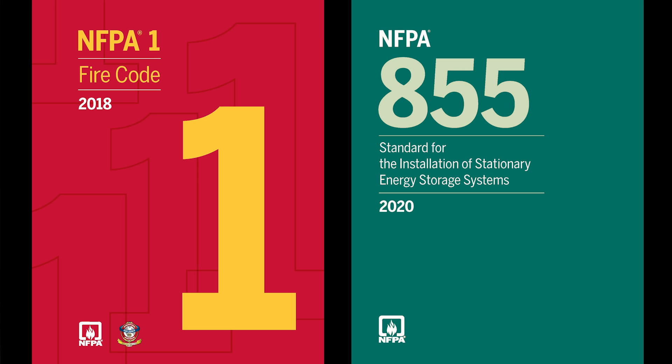The purpose of the UL 9540A test method is to ensure that the fire protection of an installation matches the hazards demonstrated in fire testing of energy storage equipment. The data from UL 9540A enables authorities-having jurisdiction, insurers, and building owners to make sure that the fire protection requirements of the installations are code and installation standard compliant. So UL 9540A evaluates the fire growth and spread potential.